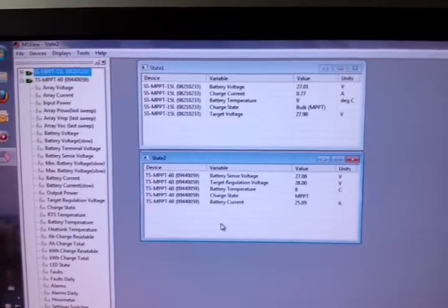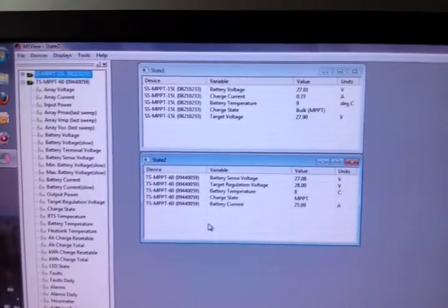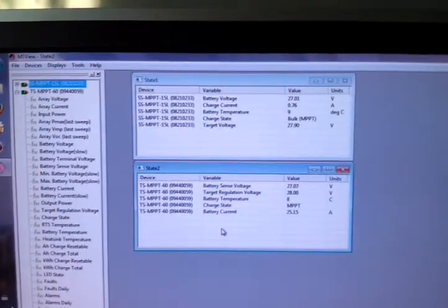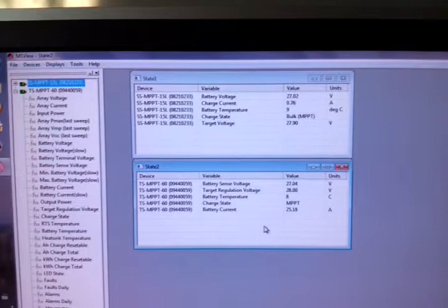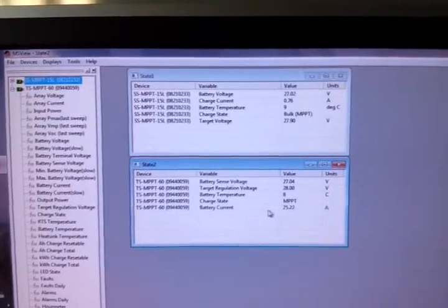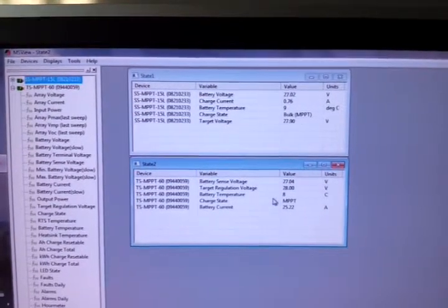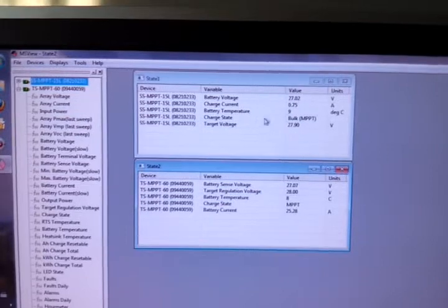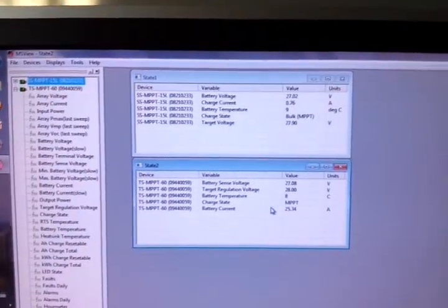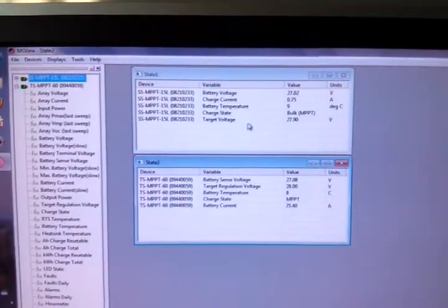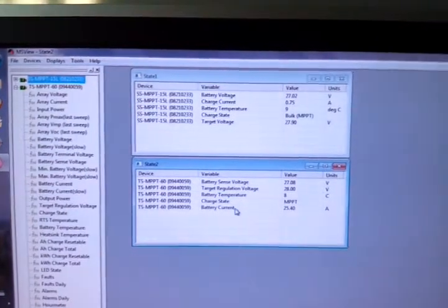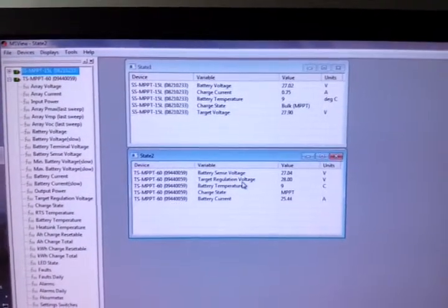But I could put the sensors on the battery pack to detect any serious fault condition, like an extremely heavy current, a short circuit, or something that was making the batteries heat up. But to be honest, it's going to take over 1,000 amps to do that. So I'm never going to see any significant temperature increase there, but the chargers are set so that above the compensation zero point of 25 degrees C, they will reduce their charge voltage at a nominal rate. Below 25 degrees C, they'll do nothing because I set the minimum temperature for the compensation effect to come into force at 25 degrees C, so it will only ever reduce the output voltage but never increase it above this set nominal value.